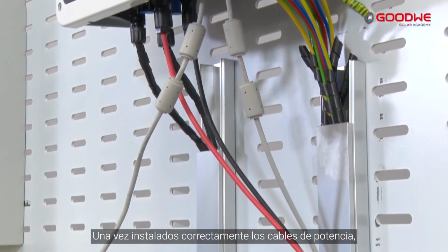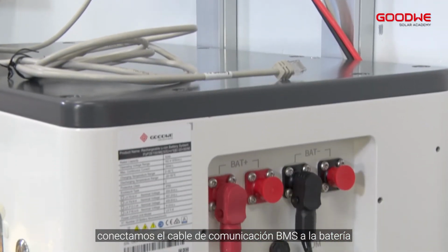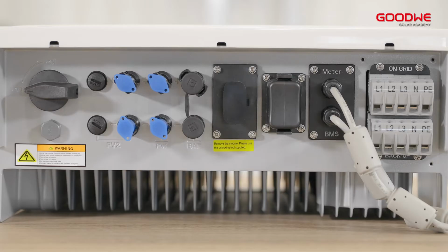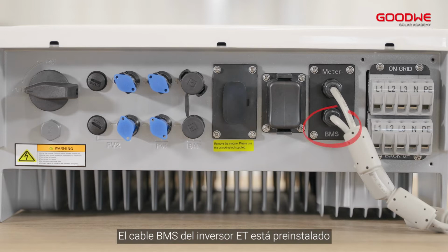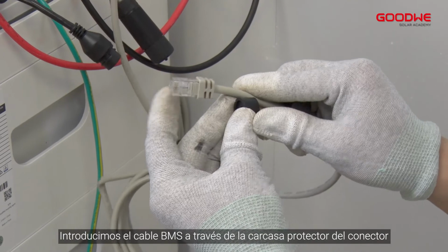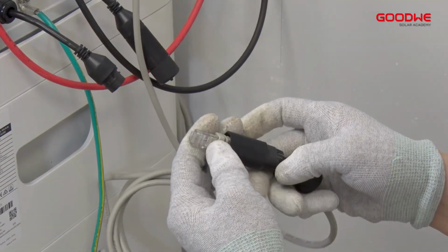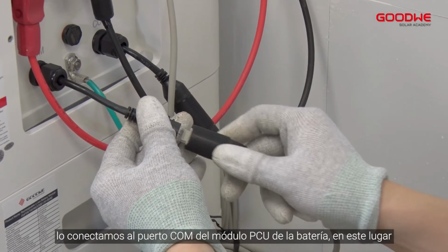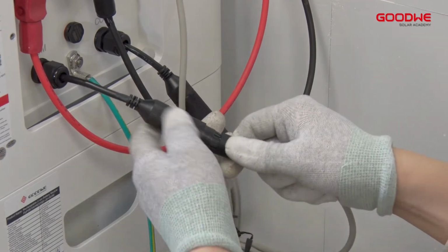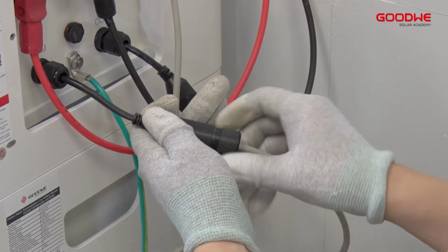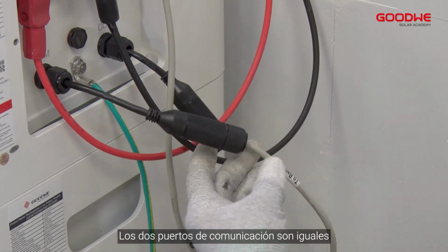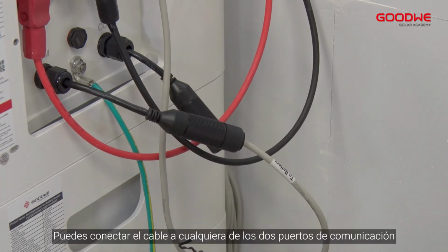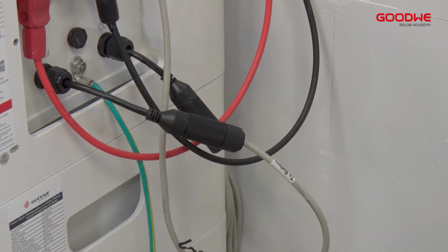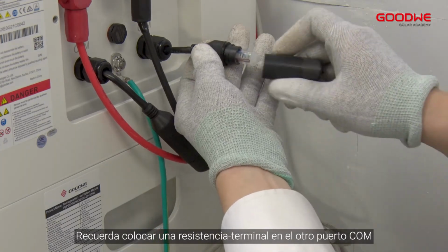After power cables are successfully installed, then connect the BMS cable to the battery. The BMS cable of the ET inverter is pre-wired and already connected with the inverter. Thread the cable to the waterproof module. Plug it into the COM port of the battery PCU box, in this place, and tighten the nut. The two communication ports are the same. You can connect the cable to any one of the two communication ports. Remember to connect the terminal resistor to the other port.